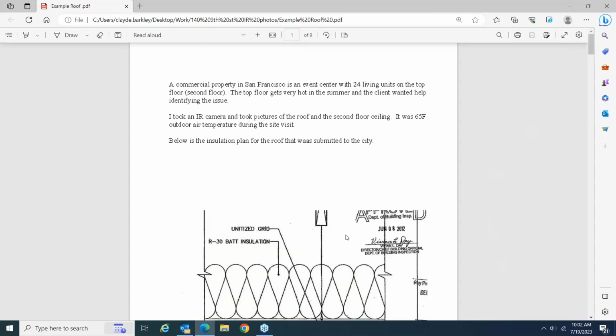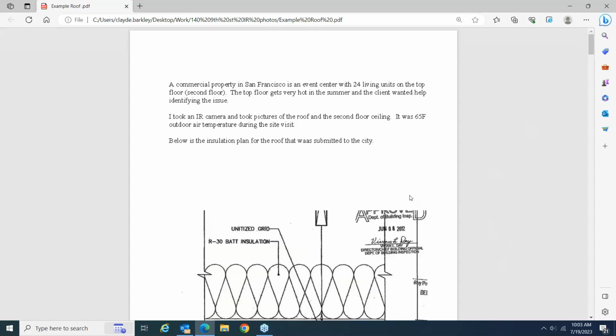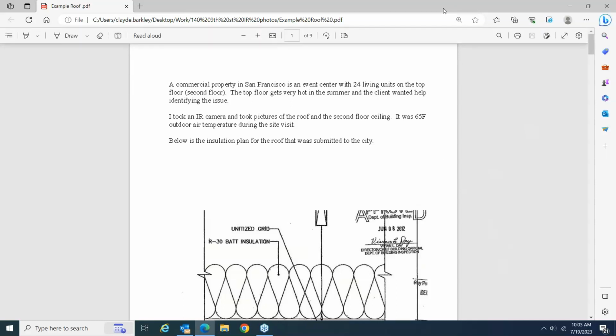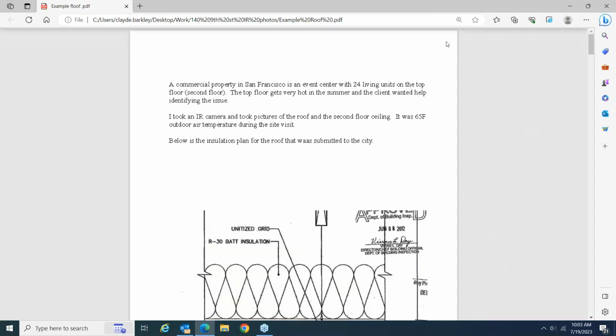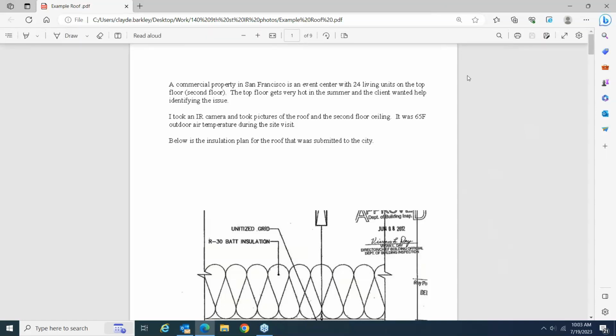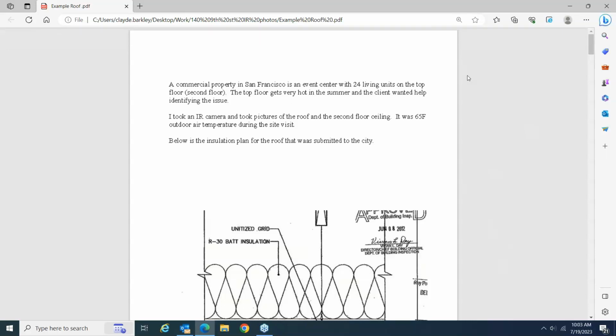Yeah, so I've been doing this about 12 years. This is the first time I've seen this. There was a commercial property in San Francisco. It has a flat roof. It's an event center on the first floor, and on the second floor there are 24 living units. And the occupant complaint is that it just gets super hot in the summer. So I took an IR camera to the building because they didn't think they had very good insulation.